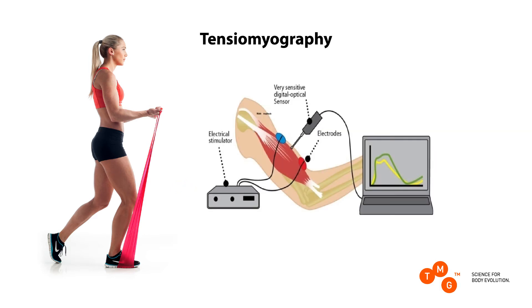The measurement protocol is very simple. It is performed in isometric conditions with the absence of voluntary involvement. To ensure objective, standardized, and repeatable conditions, bipolar electrical stimulation is used to evoke muscle contraction. The duration of a single DC electrical impulse is 1 millisecond. The electrical amplitude in milliamps is gradually increased until the supermaximal response is reached. The optical digital sensor placed over the muscle belly records the deformation of the muscle belly in the radial direction. The signal and TMG parameters are immediately displayed within the TMG software.